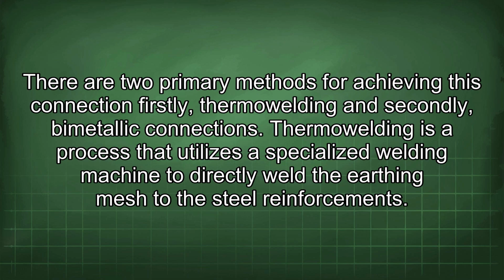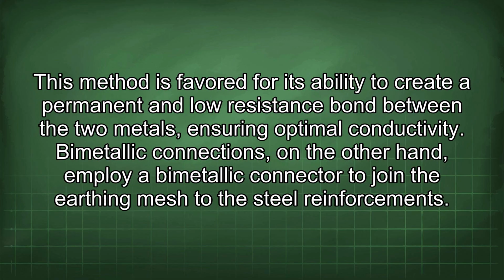Thermowelding is a process that utilizes a specialized welding machine to directly weld the earthing mesh to the steel reinforcements. This method is favored for its ability to create a permanent and low-resistance bond between the two metals, ensuring optimal conductivity. Bimetallic connections, on the other hand, employ a bimetallic connector to join the earthing mesh to the steel reinforcements.